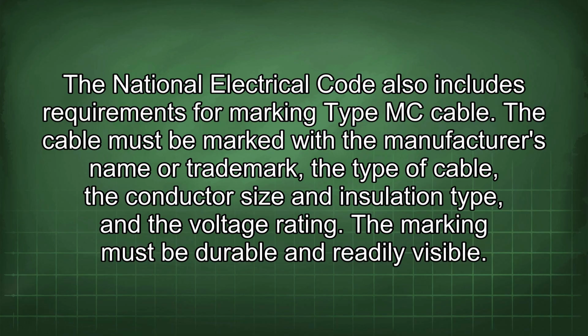The National Electrical Code also includes requirements for marking Type MC cable. The cable must be marked with the manufacturer's name or trademark, the type of cable, the conductor size and insulation type, and the voltage rating. The marking must be durable and readily visible.